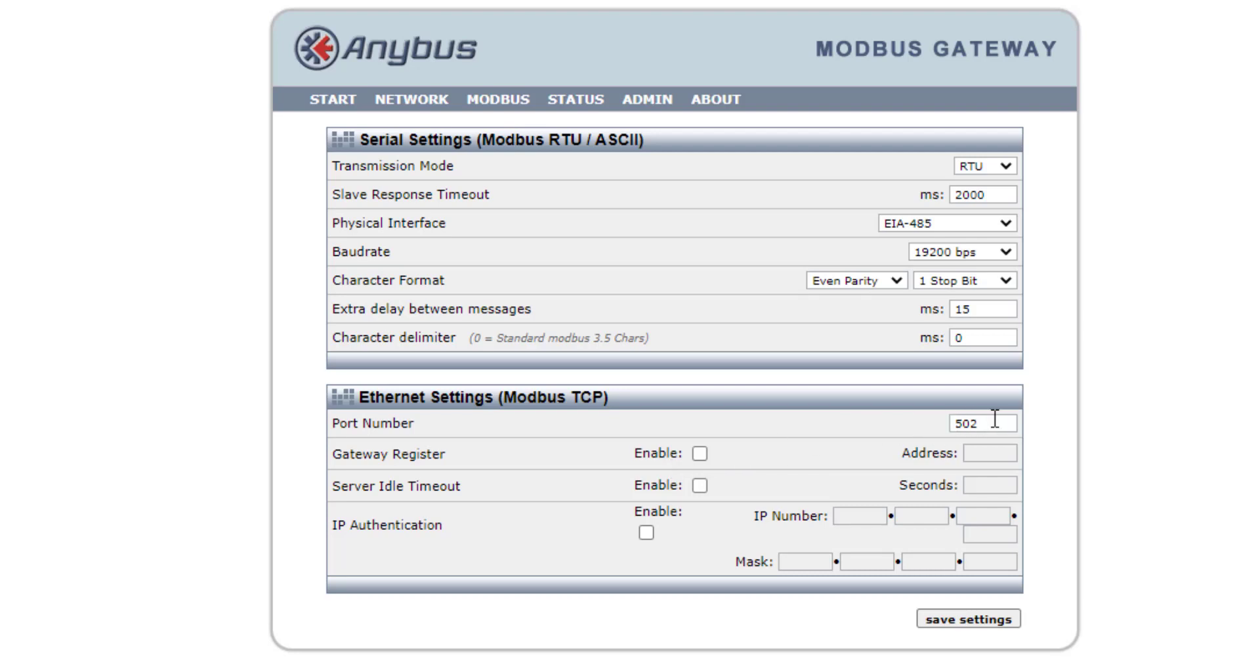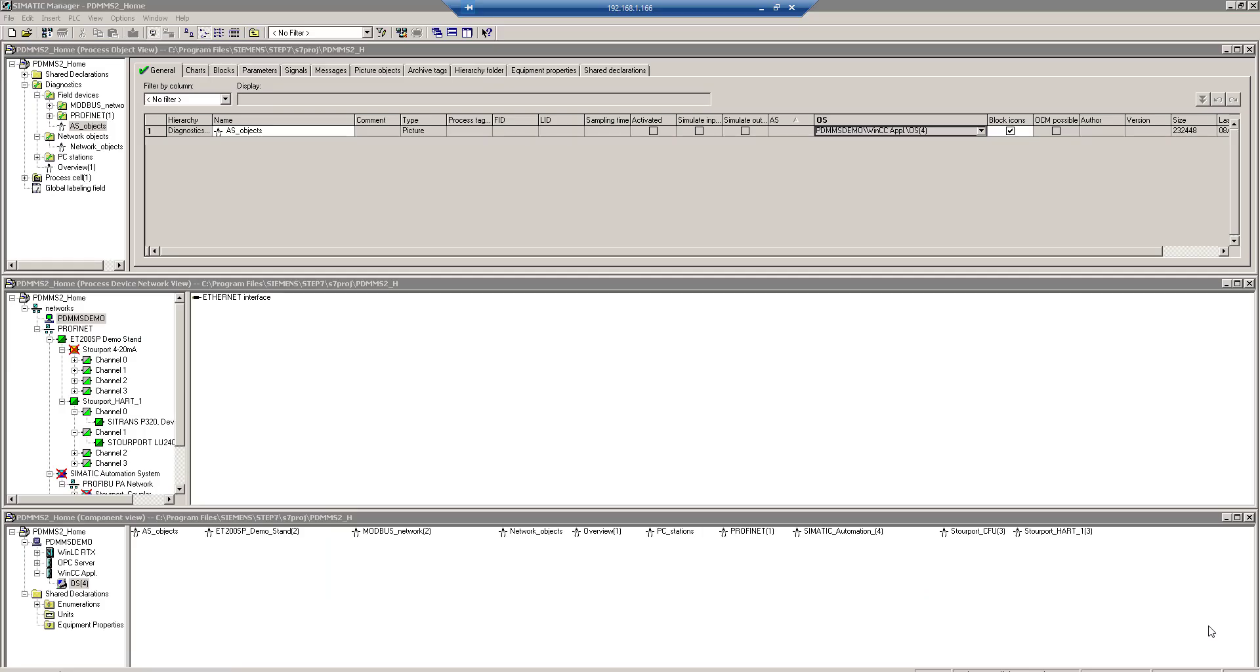502 is the default port over Ethernet for Modbus TCP. You can change that if you want, but when you come to program your TIA portal project you need to make sure it matches. So for now I'm just keeping it at default. But sometimes people like to change it to give it that added little bit of security. Once I've done that, save those settings. And as I said, make a note of the IP address. Now we're ready to set up PDM. This is my maintenance station PC, but it could be PDM standalone. Even the single tag license will support this functionality.